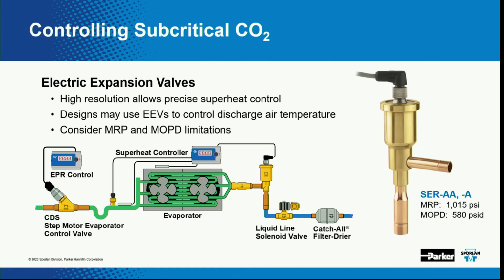We can use the EEVs to control discharge air. We can use them to control superheat. There are some other things we can do with the controllers, and I'm going to leave it at that. So that's basically just showing you this is an electric expansion valve, and this also shows an electric EPR valve on the back end to control the suction pressure or the evaporator pressure. So that could be used for like a dual case application.